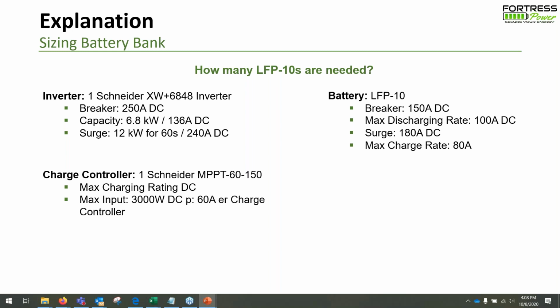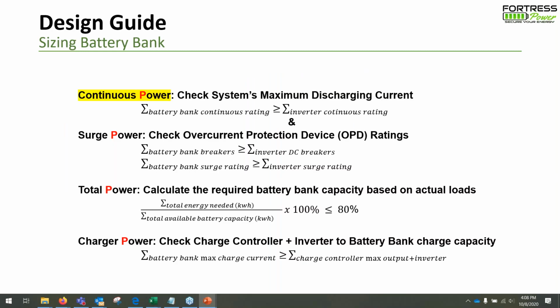The battery, the LFP10, has a breaker of 150 amps, max discharging rate of 100 amps, and the surge is 180 amps. We're not going to look at all of these specs - we're just going to look at continuous power right now. So, checking the system's maximum discharging current, because I think this is the problem that most of these systems have. We can go over the other specs independently if you want, but right now we're going to focus on continuous power.